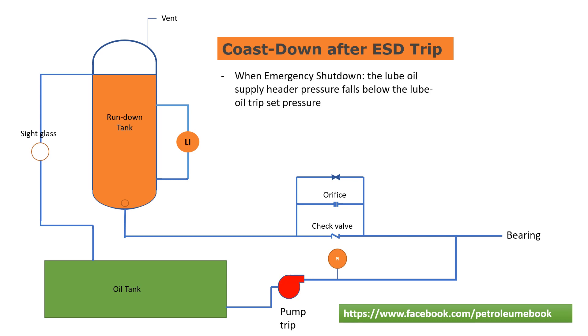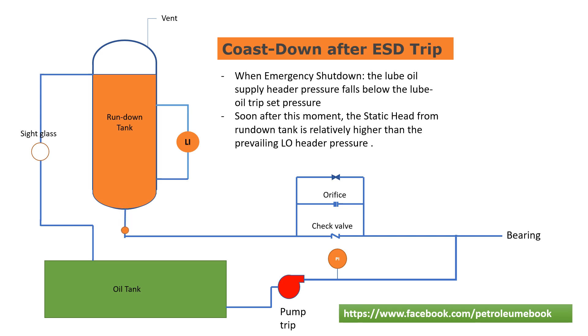When both the main and auxiliary lube oil pumps are lost, such as in the case of total power failure, the lube oil supply header pressure falls below the lube oil trip-set pressure. The main equipment trips and enters its coast-down period. Soon after this moment, the static head from the run-down tank is relatively higher than the prevailing lube oil header pressure. Therefore, a gravity flow is established from the run-down tank across the check valve down to the bearings through the lube oil supply header.